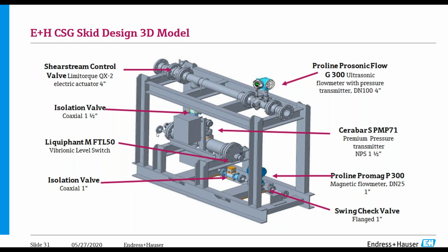Is a magnetic flow meter. So that's a tried and tested method for measuring water flow using a magnetic flow meter from Endress+Hauser. And we have all the suitable liners and electrode materials to be able to accommodate the coal seam gas industry applications. It then goes through a non-return valve, and that's there just as a safety to ensure if we get any spikes in pressure downstream that we don't have backflow coming through the skid itself.